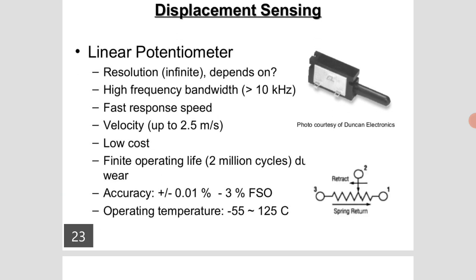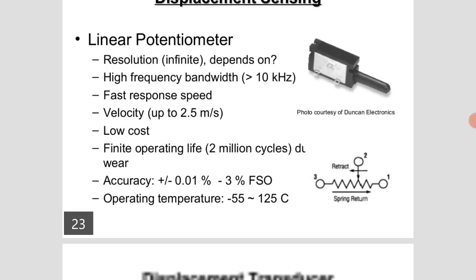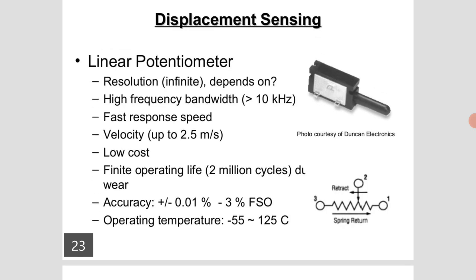Linear potentiometer: resolution infinite, high frequency bandwidth greater than 10 kHz, fast response speed, velocity up to 2.5 m per second, low cost, finite operating life 2 million cycles, accuracy plus or minus 0.01% to minus 3% FSO, operating temperature minus 55 to 125 degrees Celsius. Displacement sensing.